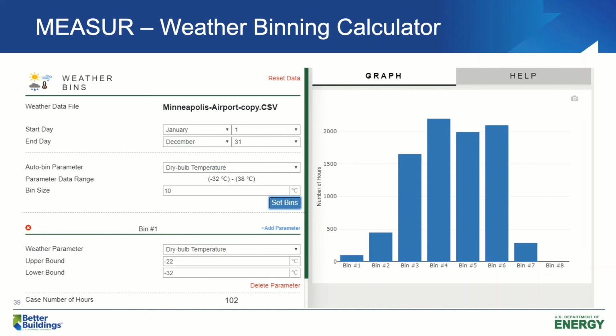The second calculator is the weather bin calculator. This calculator is very handy when you are trying to determine how many operating hours you can save from implementing weather-based controls. For example, if your spot heaters are controlled based on the outdoor air dry bulb temperature, right now the triggering temperature is set at 70 degrees, and you are thinking about changing that from 70 degrees to 50 degrees. You probably want to know how many operating hours you can save from doing that. Well, these calculators can help you out on that for sure.